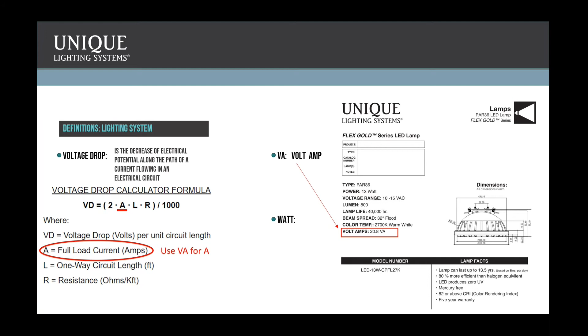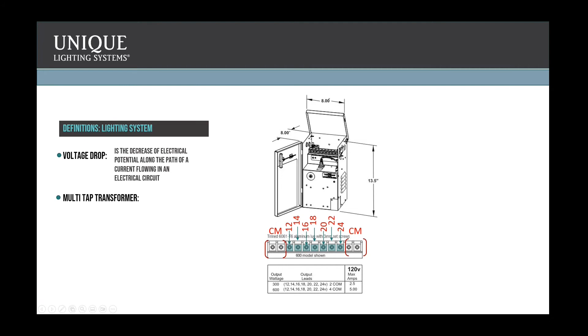Here's a diagram of a Unique 600 watt transformer, and down at the bottom we've got a detail of the lugs, or taps, as we'll call them in the webinar. This tap bar sits right up here in our transformer. These taps are arranged so that we've got a couple for our common wires, and then a 12, a 14, all the way up to a 24 volt tap.